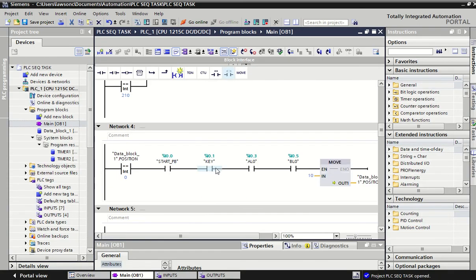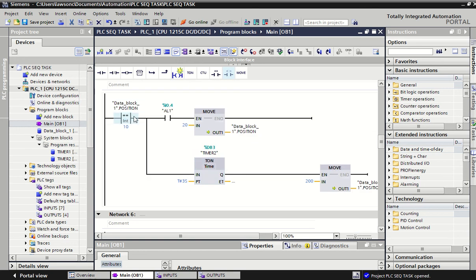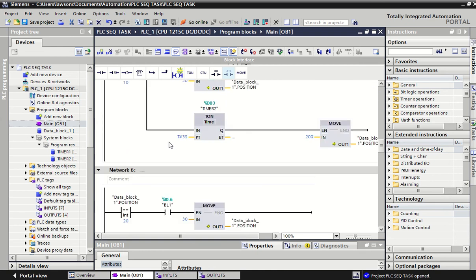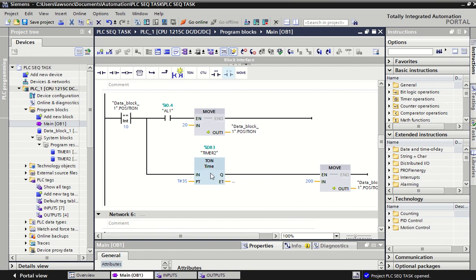It's identifying where the decision needs to occur, then coding in the two possible subsequences that could be run, or the circumstance that will do that. So if we hit the sensor in less than 3 seconds, this will finish first, and it'll just continue on with its normal sequence. But if it takes 3 seconds or more before we hit this, then it'll move to step 200.